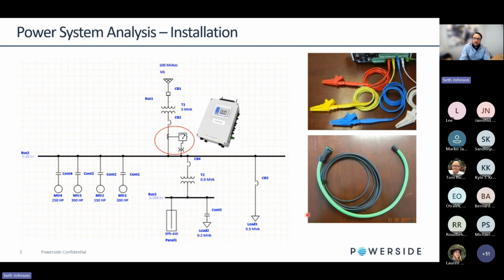And then we offer these Rogowski coil type CTs. These are great because they work for a very wide range of ampacities, specifically at low voltage. And then we can also tap into existing CTs if they are at the facility. And one of the ways we like to do that is to take a 5 amp split core style CT and just put that around one of the leads that's going to the existing CT, so that we can basically, in a very non-intrusive way, get in and get the data that we need to provide a report and hopefully propose a solution.